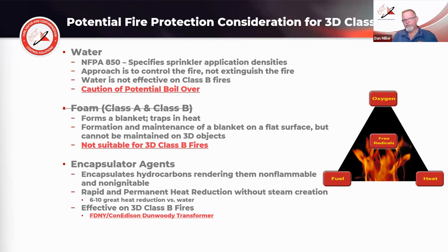So potential fire protection considerations for three-dimensional Class B fires include water. Water is what's traditionally in the sprinkler and fire protection systems for under turbine lube oil systems, but we'll show you in a minute how F500 was able to be more successful in that environment. Foam forms a blanket and traps in heat, but it's not suitable for three-dimensional Class B fires because it's spraying fuels and three-dimensional objects. You can't form a blanket on that. You would have to have a dual agent system.